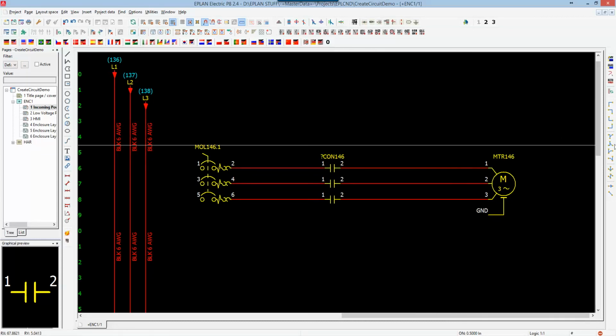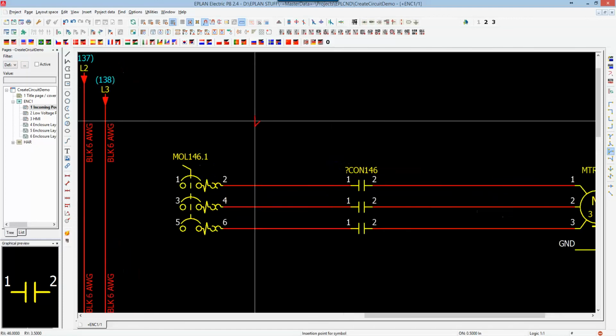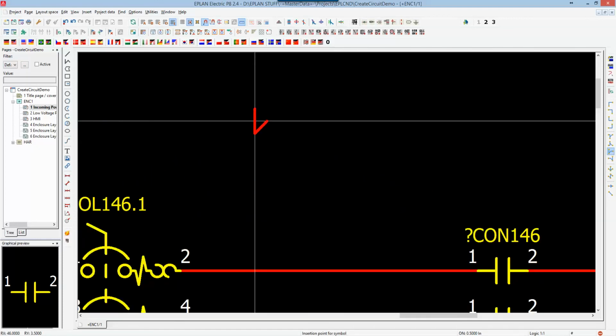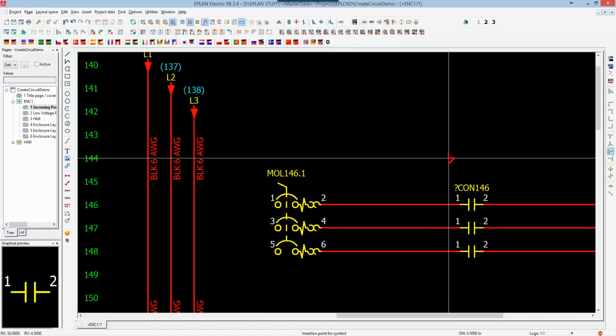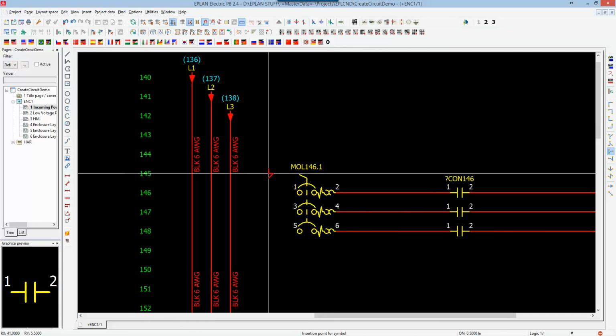So here I'm going to use some T-nodes, and under the T-nodes, I'm going to click here, and you'll notice that you have some T-node representation, and this T-node representation has multiple orientations. So this one is telling me that my source is at the bottom. There's one wire going up, one wire going to the right. If I hit the tab key, it'll shift and give me a different orientation. And I hit the tab key again, and now this one is a daisy chain type, which is sources on the top going to the right and then working its way back down, which is a daisy chain style connection.